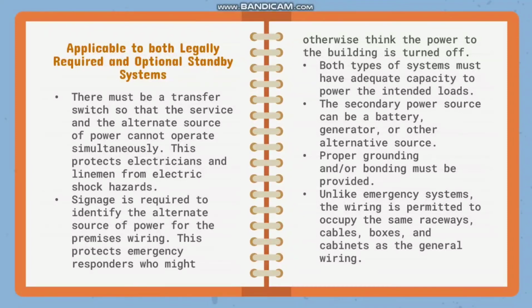Both types of systems must have adequate capacity to power the intended loads. The secondary power source can be a battery, generator, or other alternative source. Proper grounding and/or bonding must be provided, and unlike emergency systems, the wiring is permitted to occupy the same raceways, cables, boxes, and cabinets as the general wiring.